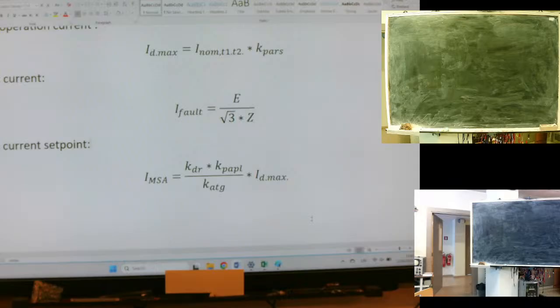So common things start to happen. They push the equipment, you push your currents. And at the same time, overcurrent protection is not the same as overcurrent protection with the possibility to activate negative sequence. Yes, negative sequence activate. Because overcurrent protection is a digital device, and you could buy a very advanced device, but the price is very different. It could be the same, but without the possibility to activate, like, directional protection, negative sequence and so on. You know where the talk is going?